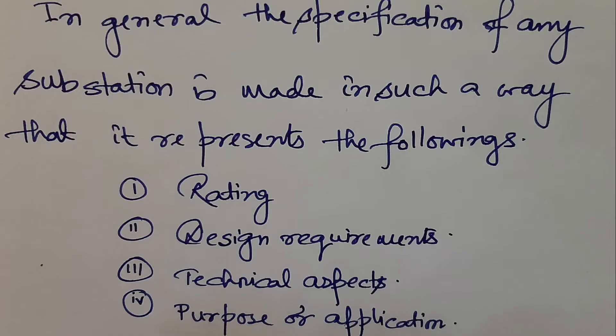While defining the specification of any substation, it shall be made in such a way that it represents at least the following: number one is rating — meaning the voltage rating, the power rating, the frequency, fault current, etc. Number two is design requirements — whether it will be indoor or outdoor type, civil facilities, and other mechanical requirements. Then the technical aspects: where it is located, the ambient conditions, and the purpose — whether it is a receiving substation, distribution substation, generating substation, or load center substation.